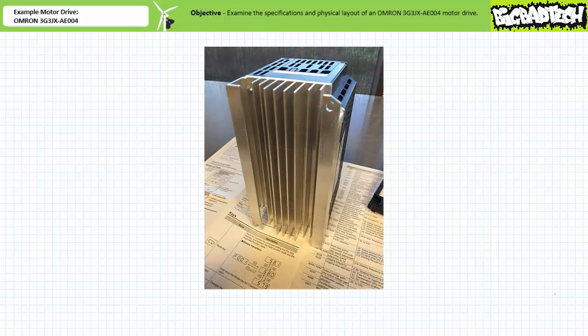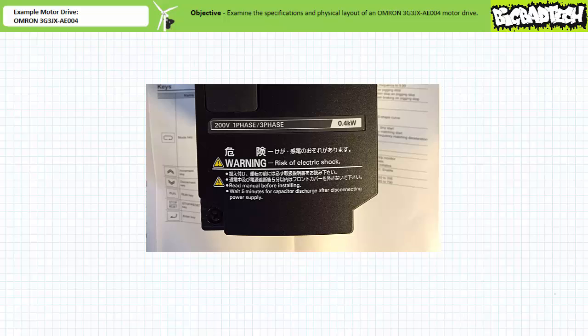When we flip the motor drive over, we see the heat sink on the back. Before we finish the external inspection of the motor drive, notice the conspicuous warning on the front panel that tells you a possibility of severe death exists if you don't wait for the motor drive to discharge a specified length of time after disconnecting it.